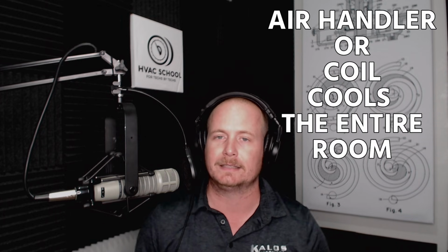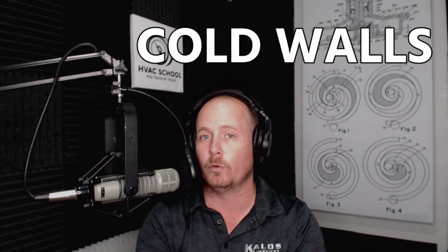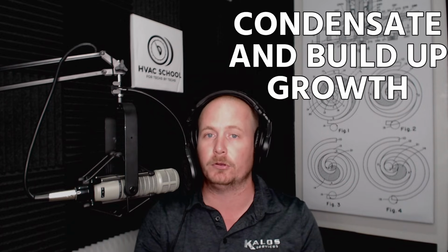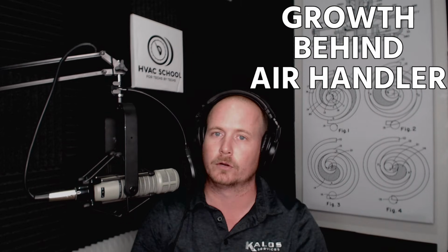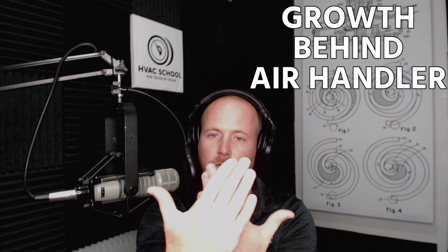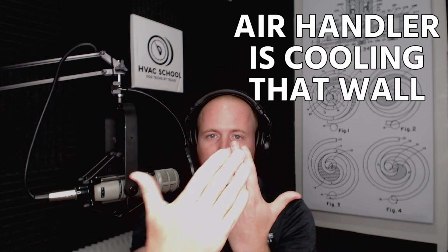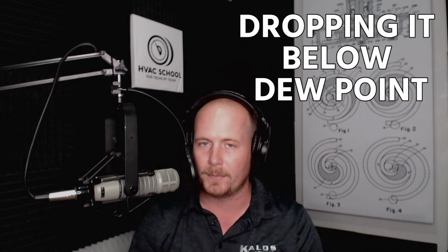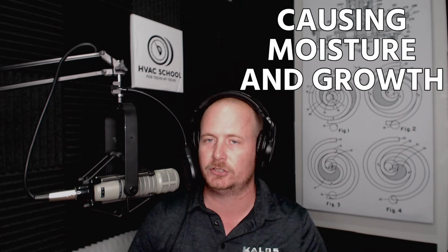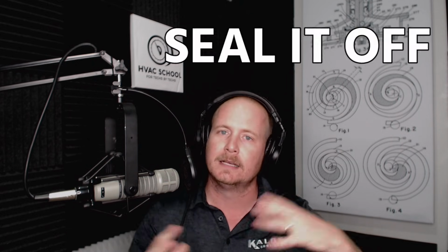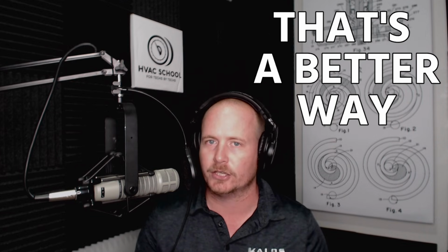radiantly cools that entire room. Often that will create cold walls that will then also condensate and build up growth. This is where sometimes you'll remove an air handler and you'll notice that there's all this growth right behind the air handler where it was next to the wall, and that's because that air handler is radiantly cooling that wall, dropping it below dew point and causing that moisture and that growth. What I often suggest, if you're going to have them in enclosed spaces like this, is seal it off, insulate it, and condition it. That's a better way.